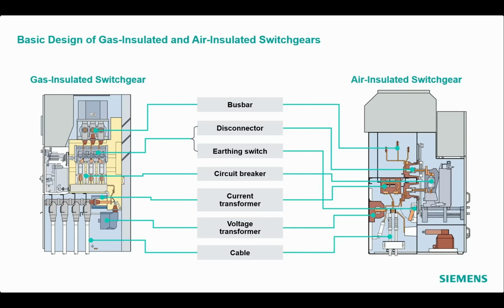Let us start from the top. Here one can refer to the bus bars comprising the three phases which carry the current. This is followed by the disconnector and earthing switch. In case of GIS, this functionality is provided generally by a 3-position switch present inside the gas compartment. In case of AIS, the disconnection is provided when the shutters are closed, and the earthing functionality is provided by an earthing switch.